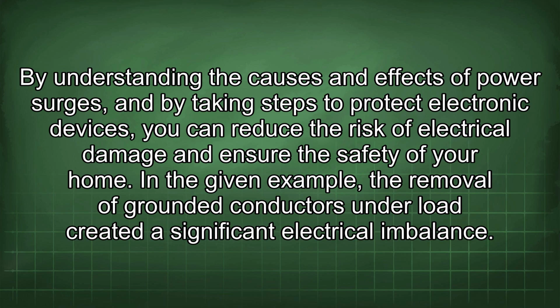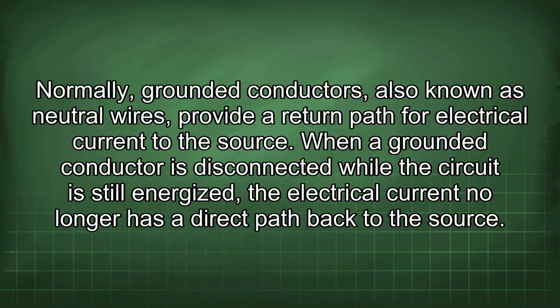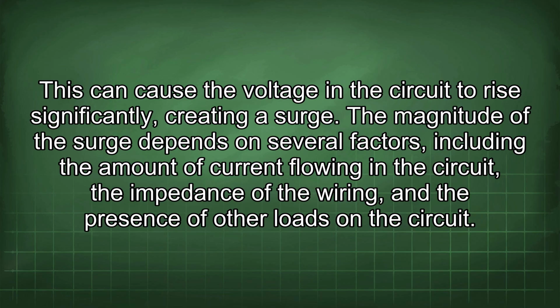In the given example, the removal of grounded conductors under load created a significant electrical imbalance. Normally, grounded conductors, also known as neutral wires, provide a return path for electrical current to the source. When a grounded conductor is disconnected while the circuit is still energized, the electrical current no longer has a direct path back to the source. This can cause the voltage in the circuit to rise significantly, creating a surge. The magnitude of the surge depends on several factors, including the amount of current flowing in the circuit, the impedance of the wiring, and the presence of other loads in the circuit.